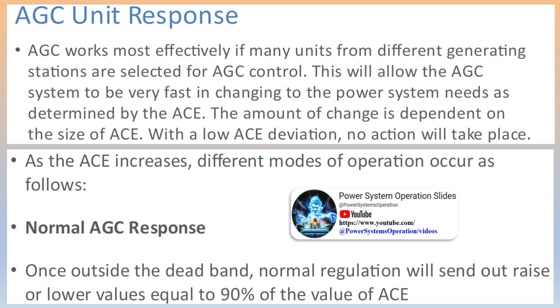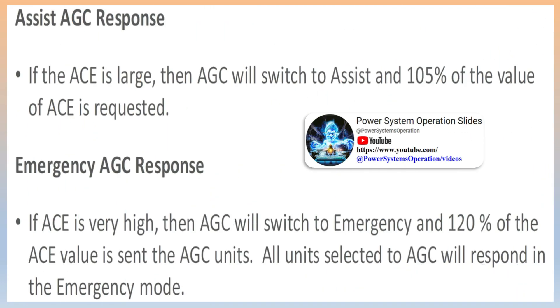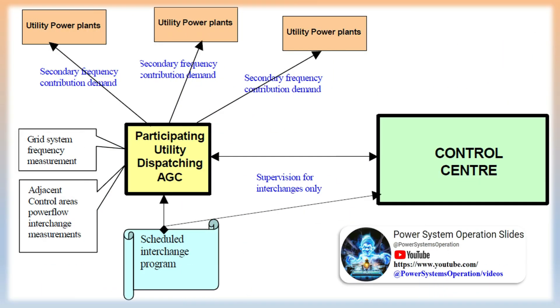Other problems which could cause AGC to suspend may be tie-line telemetering giving bad data due to failed communication, testing, or commissioning new points. All of these should be considered before AGC is put back into automatic operation. The generation dispatcher must have sufficient units on AGC to provide load-following reserves in addition to contingency reserves. This is required to be able to send control setpoints up or down to satisfy ACE regulation control expected in the next period.